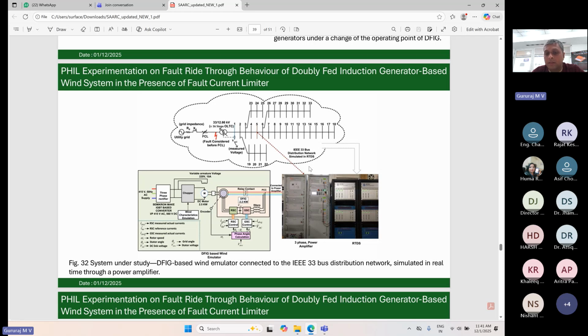So one of the research challenges which is predominantly studied by various researchers across the globe with respect to this type 3 wind energy conversion system is fault ride-through. So if there is a fault on the stator side, maybe a remote fault on the grid, what happens is the grid voltage collapses. The flux, being the state variable, does not allow sudden transition. The rotor is rotating because mechanical inertia is there, but the stator flux dips. So there is a constant flux now seen from the rotor side.